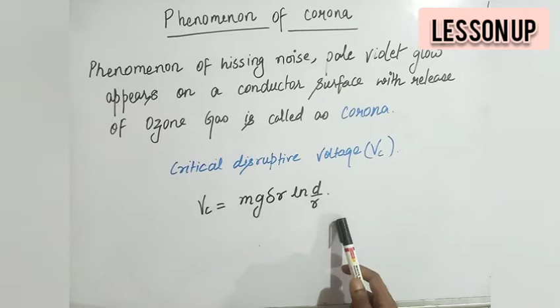Vc is equal to m g delta R ln d by R, where m is the irregularity factor. The value of m is 1.0 for a polished surface. It can be 0.98 to 0.92 for a dirty surface. It can be 0.87 to 0.8 for standard conductors. Basically you can take 1 for a polished surface, and for other conductors it can be taken as less than 1.